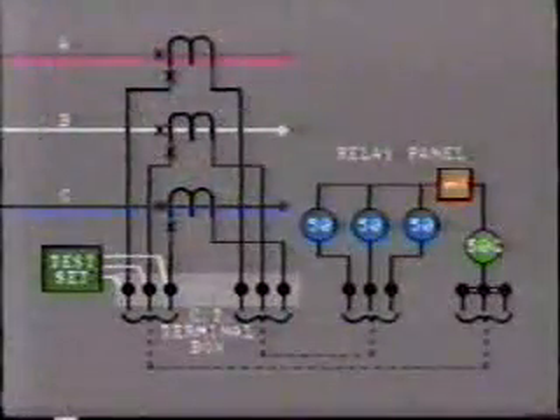One way of checking CT connections is by injecting three-phase test current into the three phases of the CT secondaries. Measurement at the relay panel will then establish that CTs are connected to the corresponding phase relay, and residual current measurement will prove that they are connected the right way around. Many companies check out CT connections by primary injection tests. In this method, low voltage test current is passed through the primary conductors themselves, and measurements are taken on the secondary side to prove that the CT connections are correct.